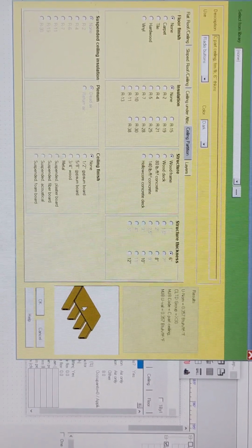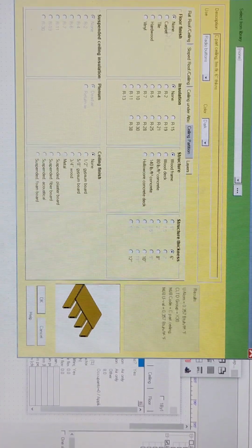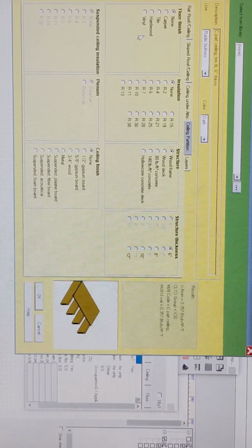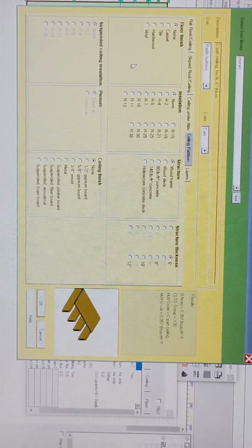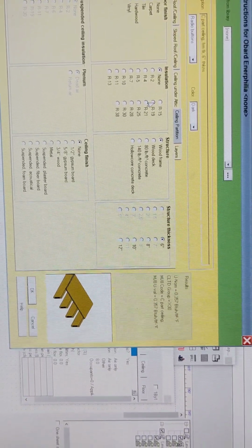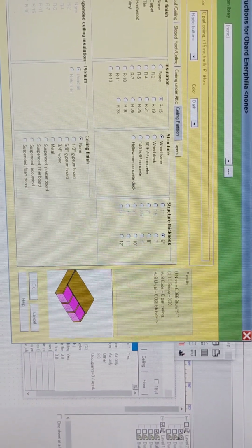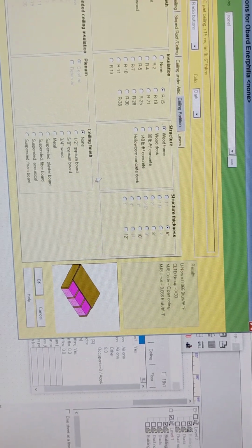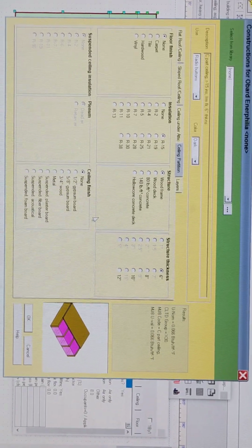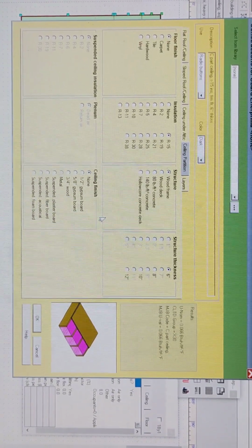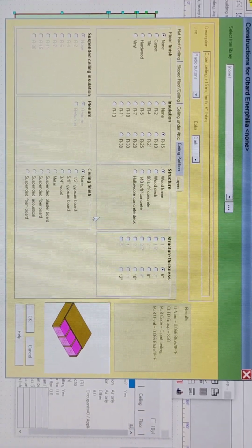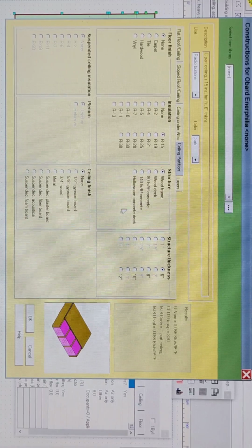Again, you have to have certain information that sometimes I won't have. So we're going to use none here just because I don't know if they're carpet, tile, hardwood, and all of that changes how air passes from one to the other. They'll have R15 between the two. It's hard to get R19 into a 2x4 space, so almost the only way to do it is spray foam, and a lot of time they don't like using spray foam between floors because it doesn't kill the noise, so we'll use R15 because they'll probably be using batts.